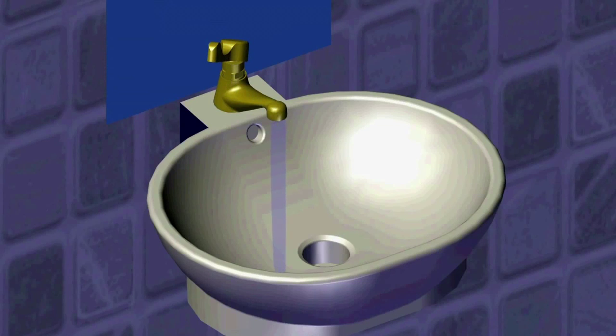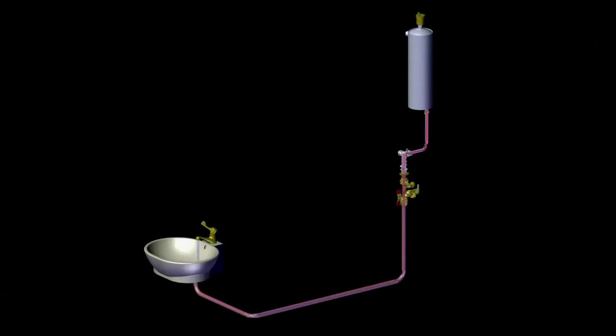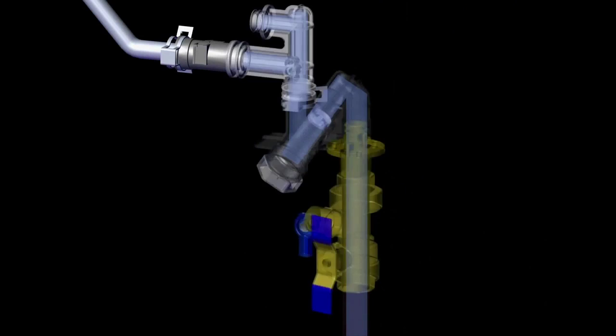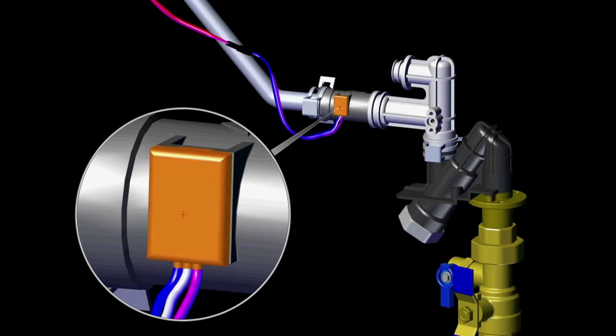During central heating mode, central heating is temporarily stopped by the movement of the three-way valve to divert the heated water to circulate back through the internal storage tank, providing priority and large amounts of domestic hot water production. When the consumer uses domestic hot water, direct city water enters the domestic hot water heat exchanger, which is detected by the flow sensor.